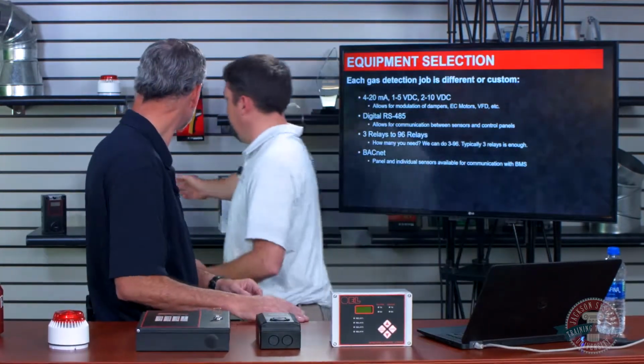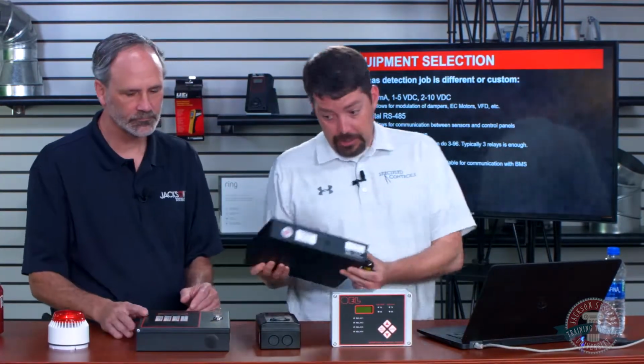But we're capable, we can actually add a relay panel. We can add multiple relay panels to this panel. And the relay panels, there's nothing exciting to show you. There's just a bunch of relays in it. We can do up to 96 relays off 1 panel. So we can do all kinds of crazy stuff. We can start turning on Christmas lights and whatever you want. Based on CO level? Yeah, why not? Sure. But we can do all kinds of things. So just know that there is no real limitation to the panels that we can offer in terms of what they can do and what they can bring on or zone in terms of fans and louvers and things.